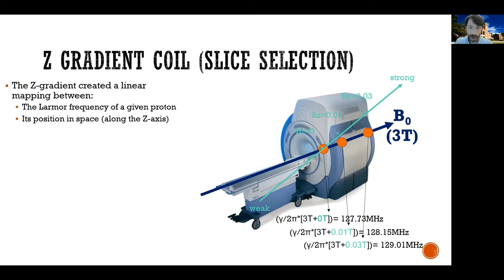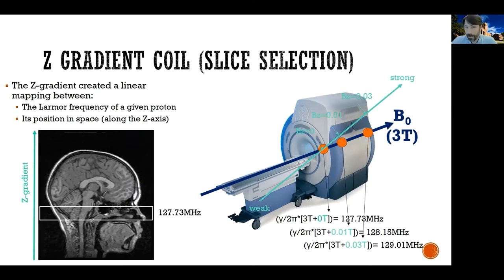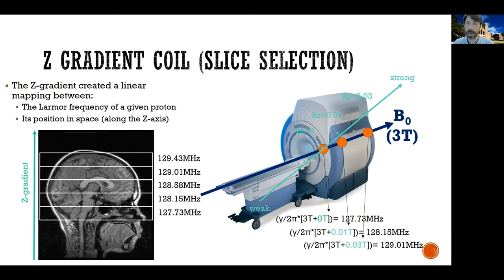I've managed to divide my protons along one direction so I can select which proton to excite with the radio frequency pulse. For example, say the Z gradient goes from the bottom to the top of the head. Protons down here resonate at 127.73 MHz, the next level at 128.15, then 128.58, 129.01, 129.43, and so on. Thanks to the Z gradient, I can decide to excite only protons from one of these slices — that's why we call it the slice selection gradient.